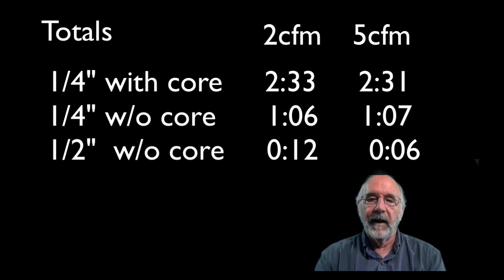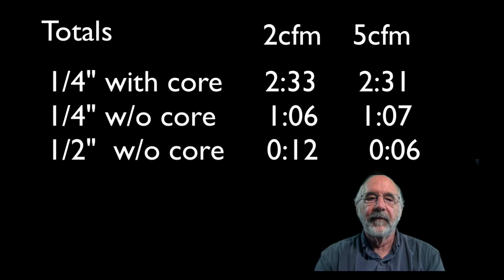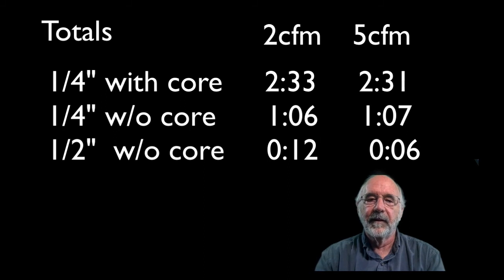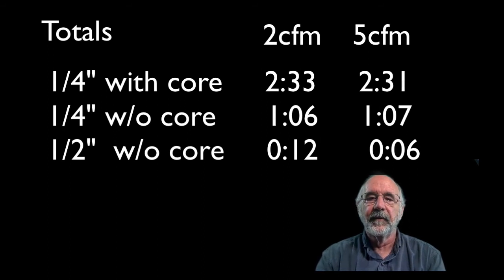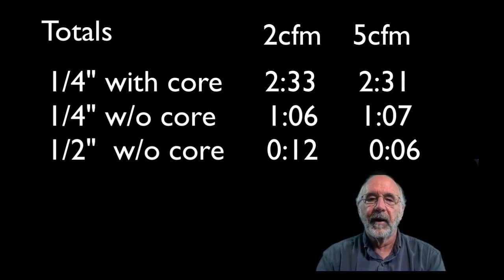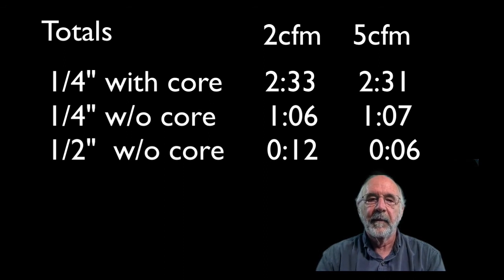With no Schrader using a half inch diameter hose, that made a huge difference: 12 seconds for the 2 CFM pump, six seconds for the 5 CFM pump.